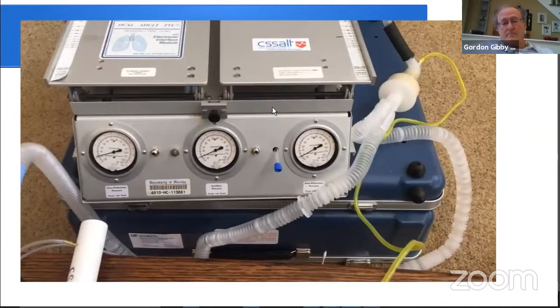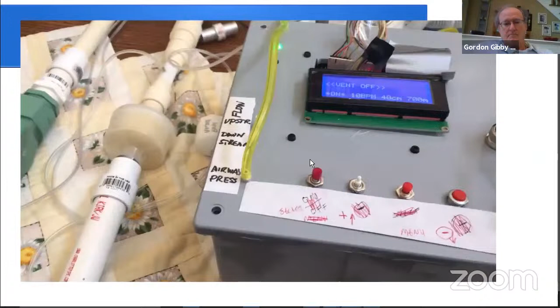The screen on the front of the ventilator, we're just using 1/2, shows the pressure on an analog dial that does not follow at all the fast transients that we actually see. That yellow fuel tubing is an airway pressure tap that goes into a Bosch BMP 280. And the air comes back from the patient into this part of the system.